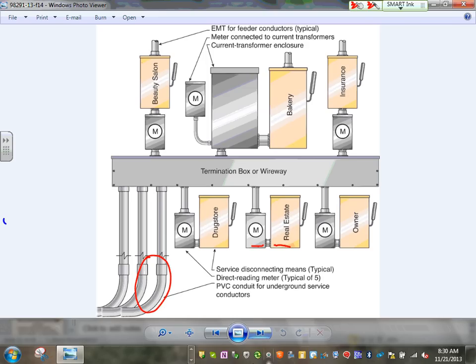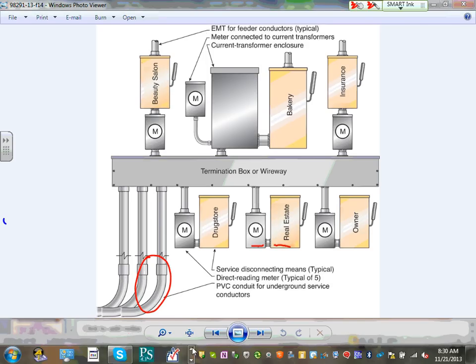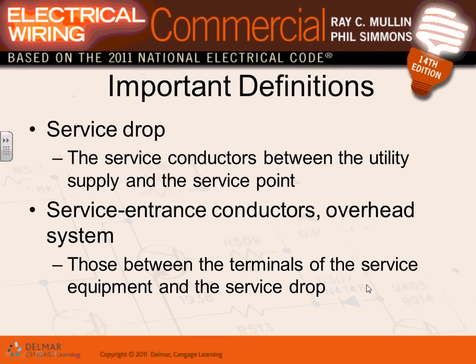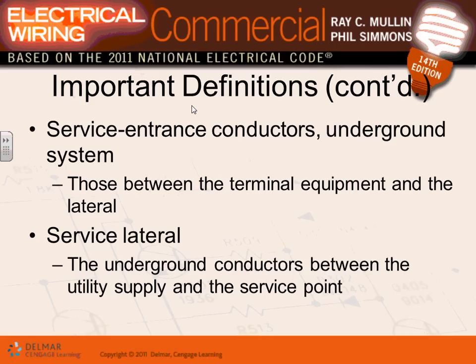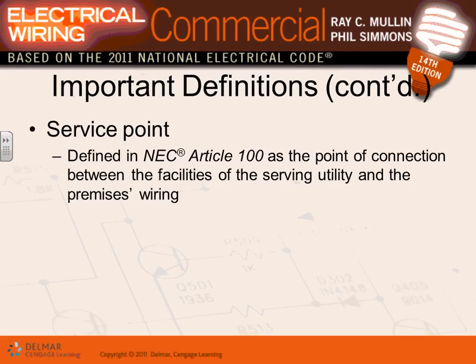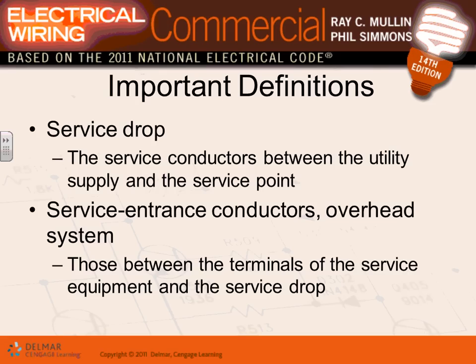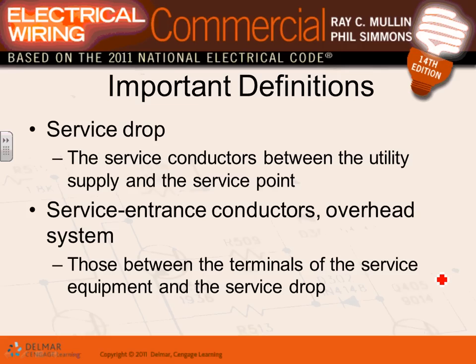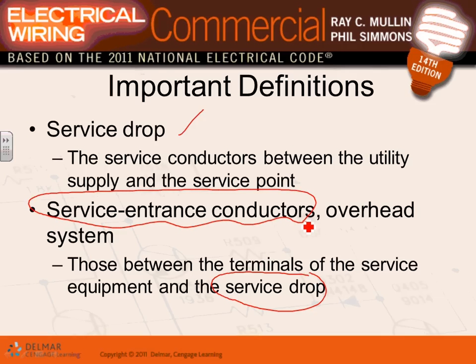Okay, so that's a few of these, the service point and what's not. Okay, that's the service drop. The power lines are coming to your building. Like I said, they're called service drop. These are just a couple of terminologies that they use, and again, we did them in the residential. The power coming to your building is called service drop. Service entrance conductors take you from your service drop into your equipment. That's called service entrance conductor. These are what we care about. We size these. Service entrance conductor, Adam, you size it. These are the cables for the 500 amp that you brought to me on your table. You call them service entrance conductor.